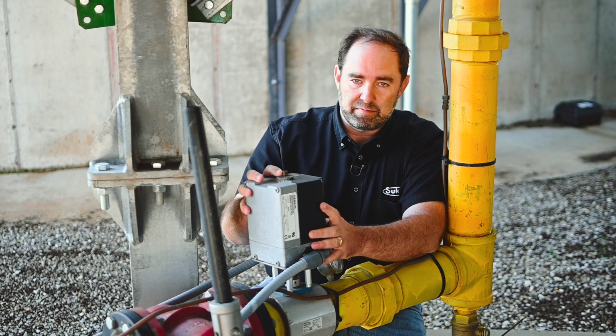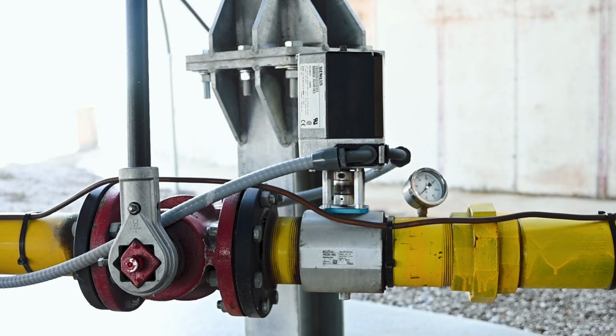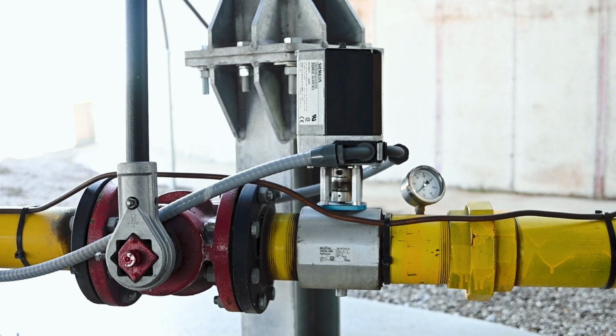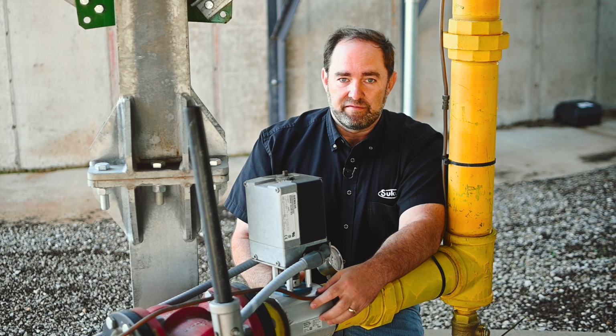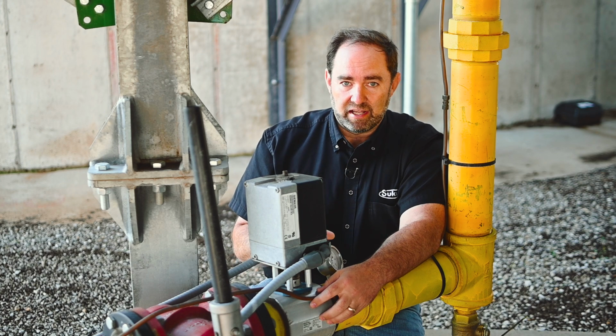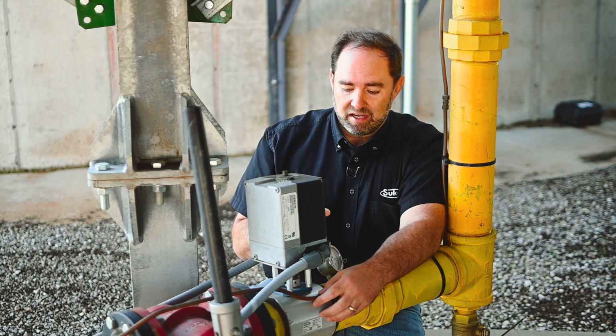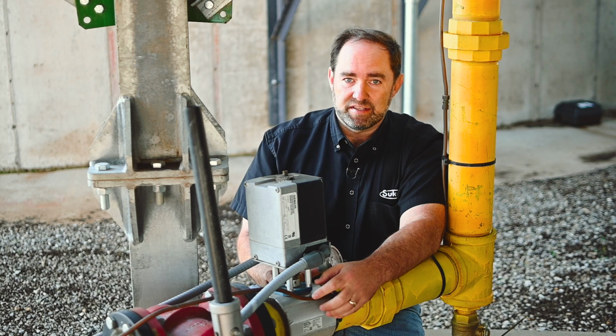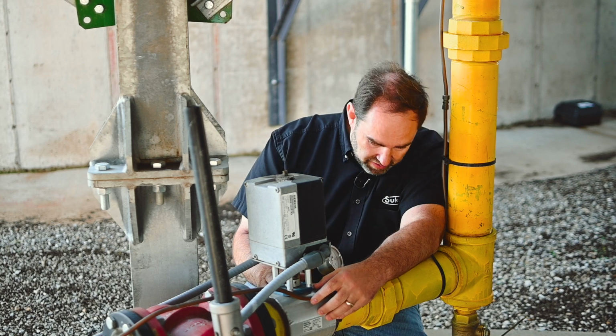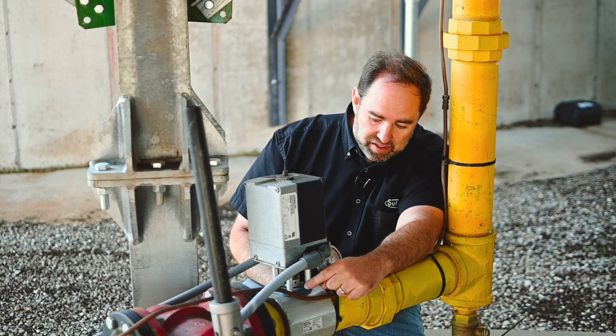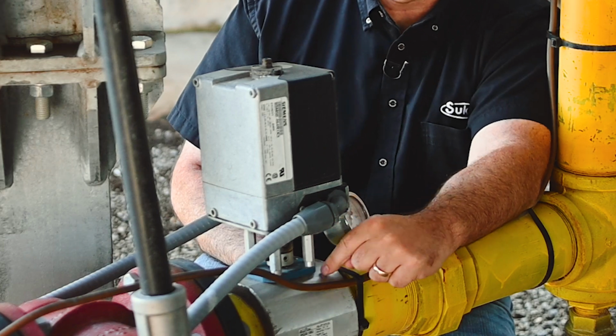And the black thing on top of it is an actuator motor. So that opens and closes that butterfly valve. These can be a little bit fragile. If water was to get in the system or allowed to be in the system and freeze, one of the first things that could have a problem is this butterfly valve. And there's an indicator here showing its position from 0 basically to 90 degrees, you'll see on there.